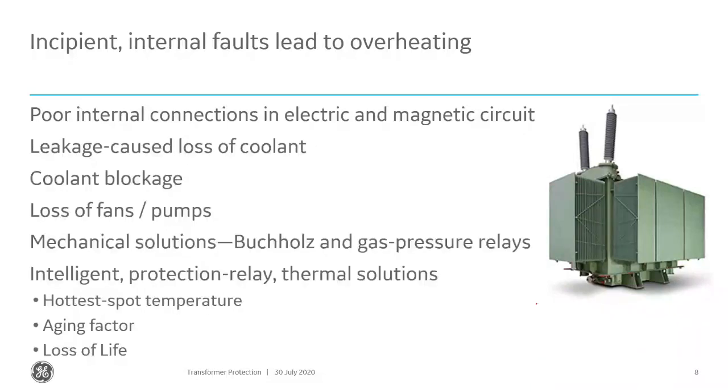Now, we can't really do that with a relay from an electrical measurement, but we can do that from a hot spot temperature calculation, or not calculation, but actual measured hot spot temperature from the RTD.